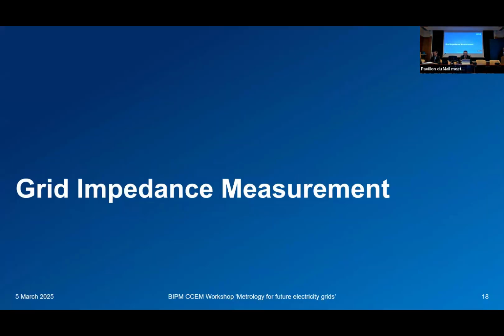And then I did touch upon grid impedance. Grid impedance is highly important both for supraharmonics, in the 2 to 150 kilohertz frequency range, but also when we think about those subsynchronous oscillations. The extent to which they persist very much depends on the damping. If we have a lot of damping, usually the oscillations will go away quite quickly on their own. So for network operators, if they want to try to prevent some of these transients in the first place, rather than waiting for them to happen, they need to understand in advance the sensitivity of the system to react in such a way. And that's where the grid impedance becomes an important factor.